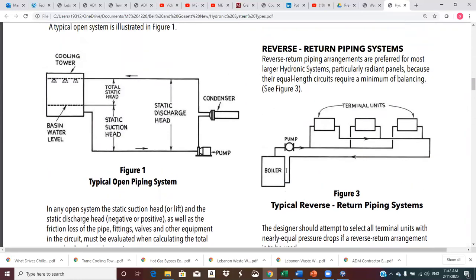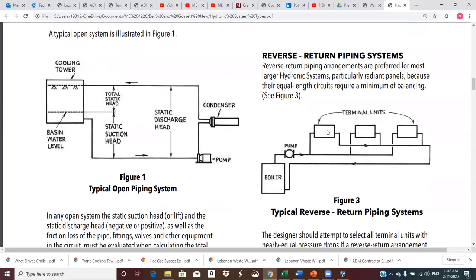The idea here, this will be somewhat self-balancing. If these have the same pressure drop, they have approximately the same path length. And if these are also equal pressure drops, then you turn this thing on, you won't have much trouble balancing, getting the proper flow to each of the coils.